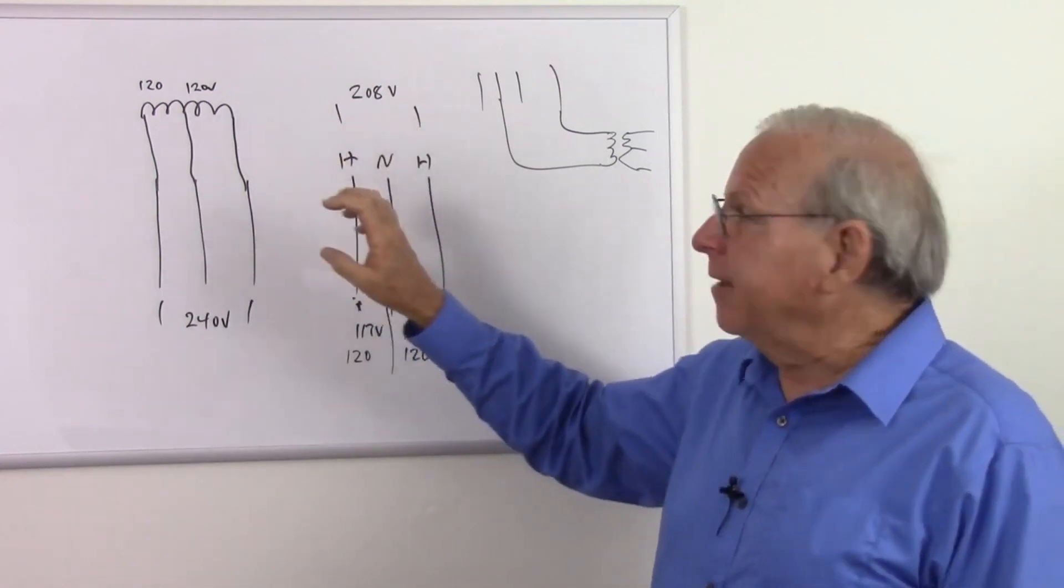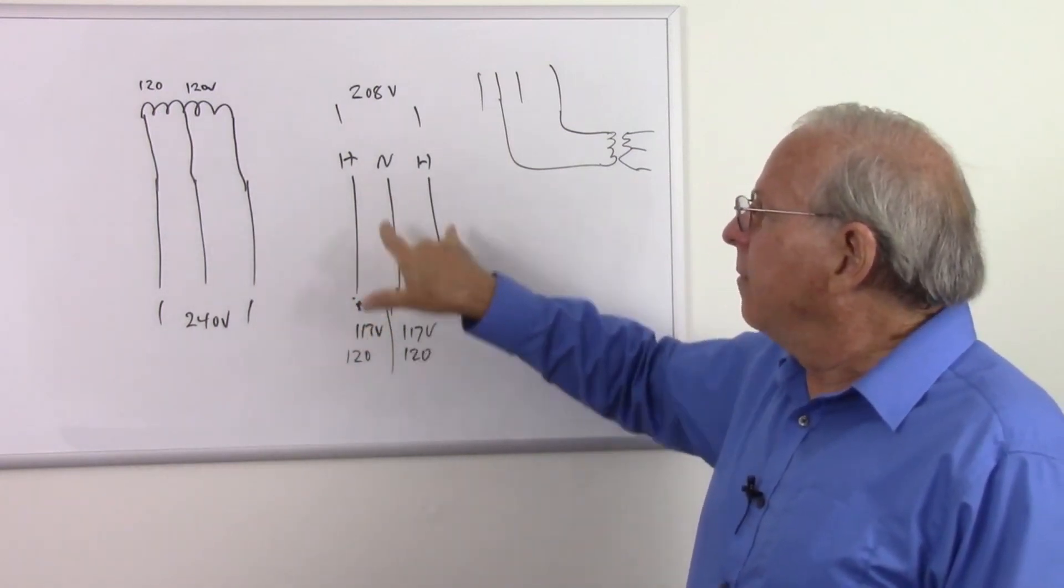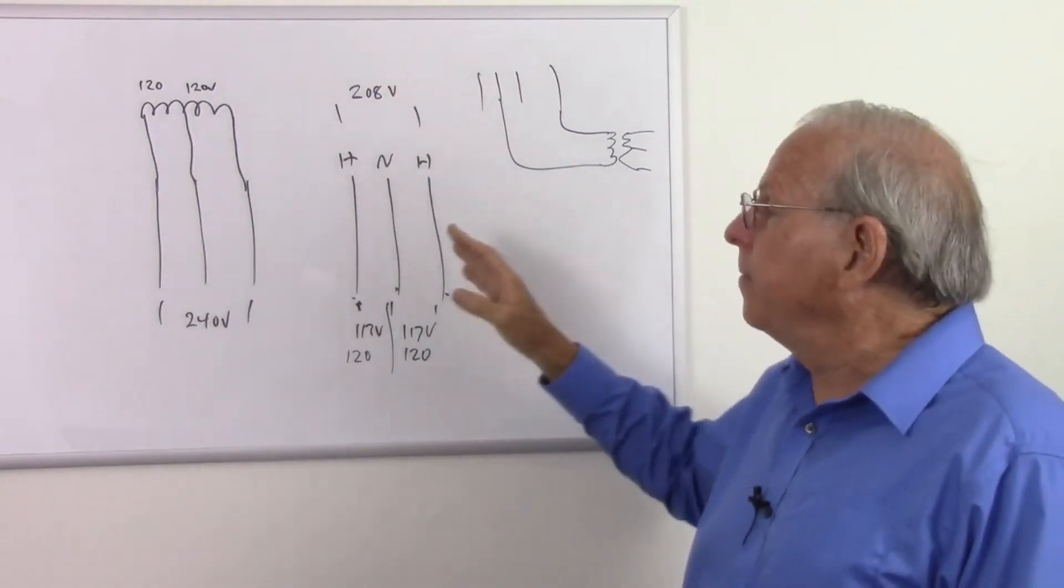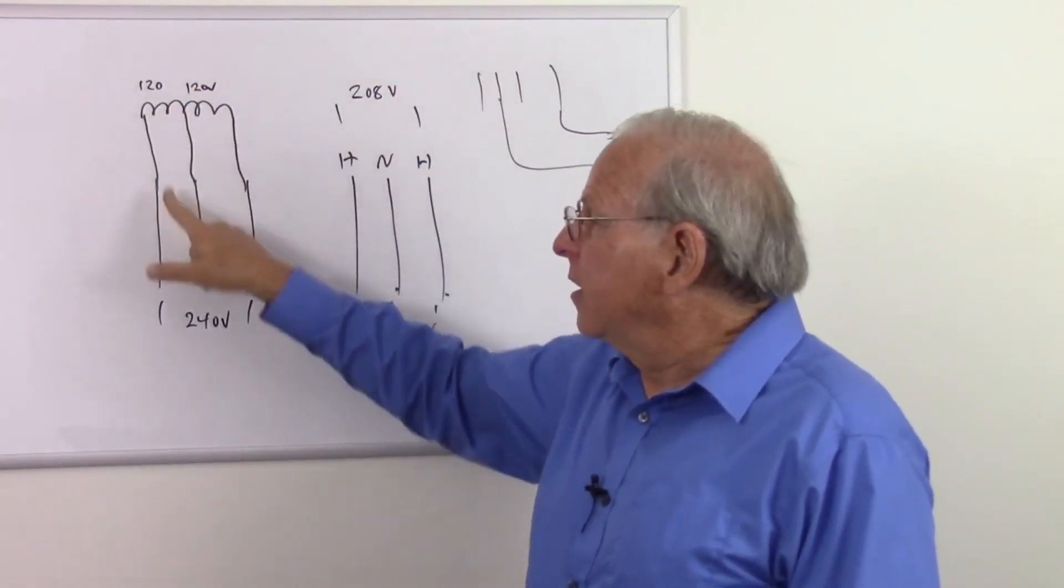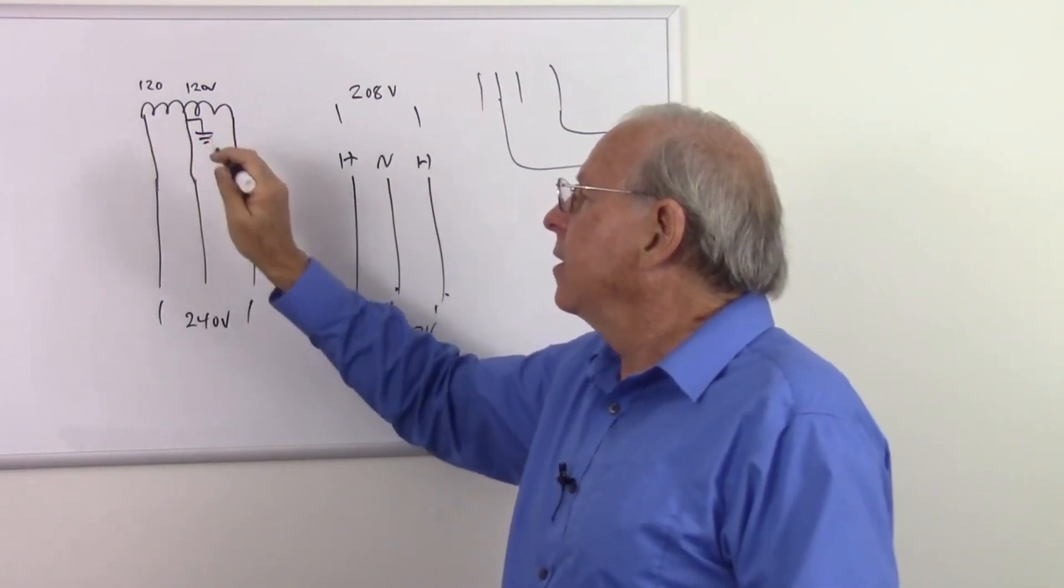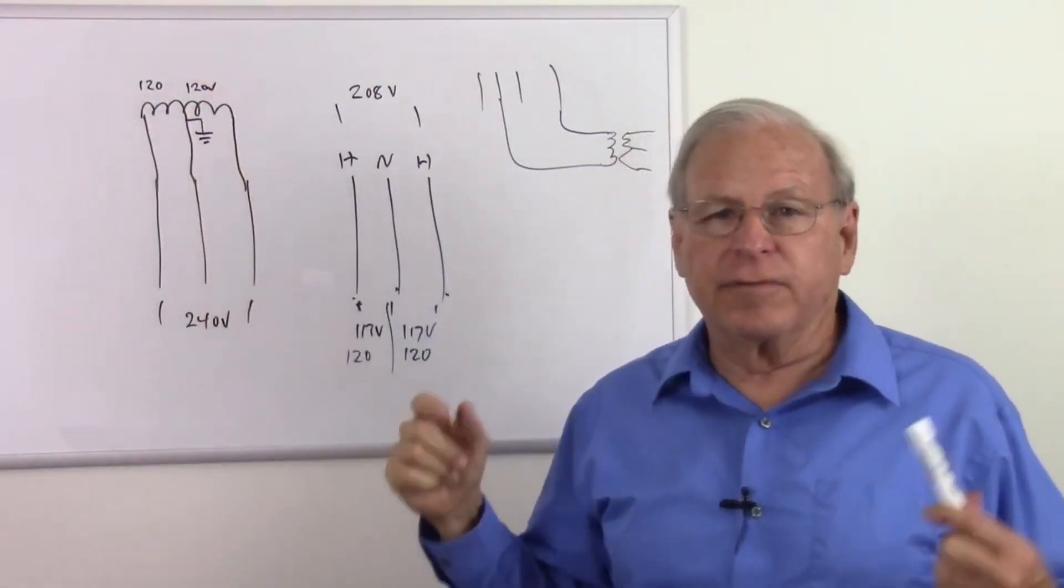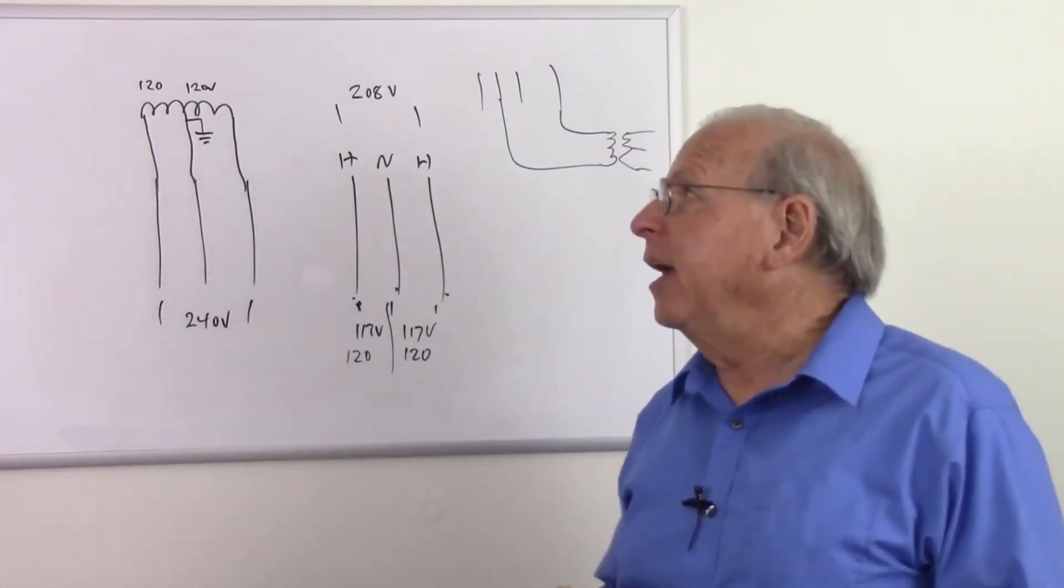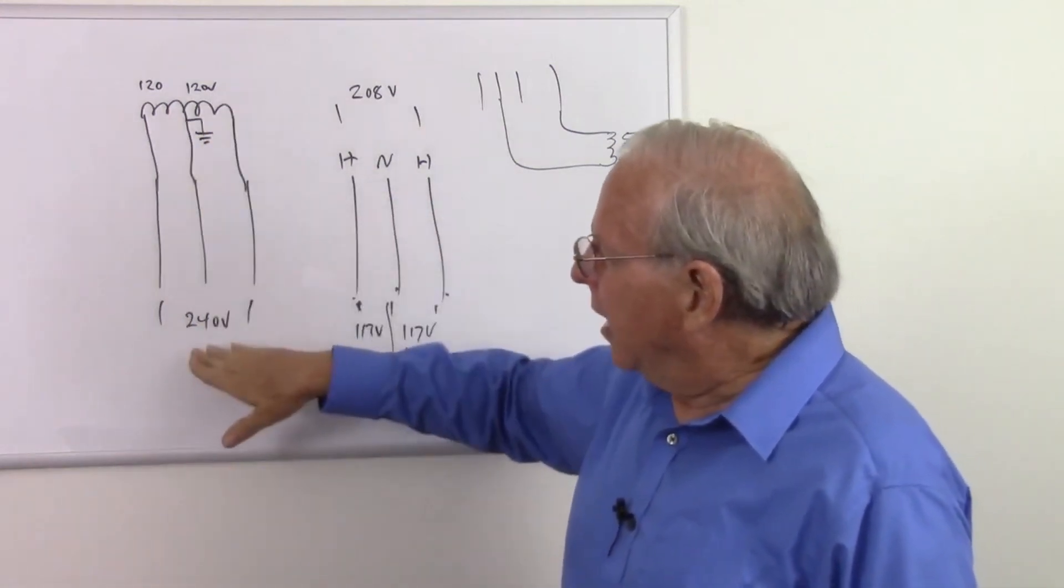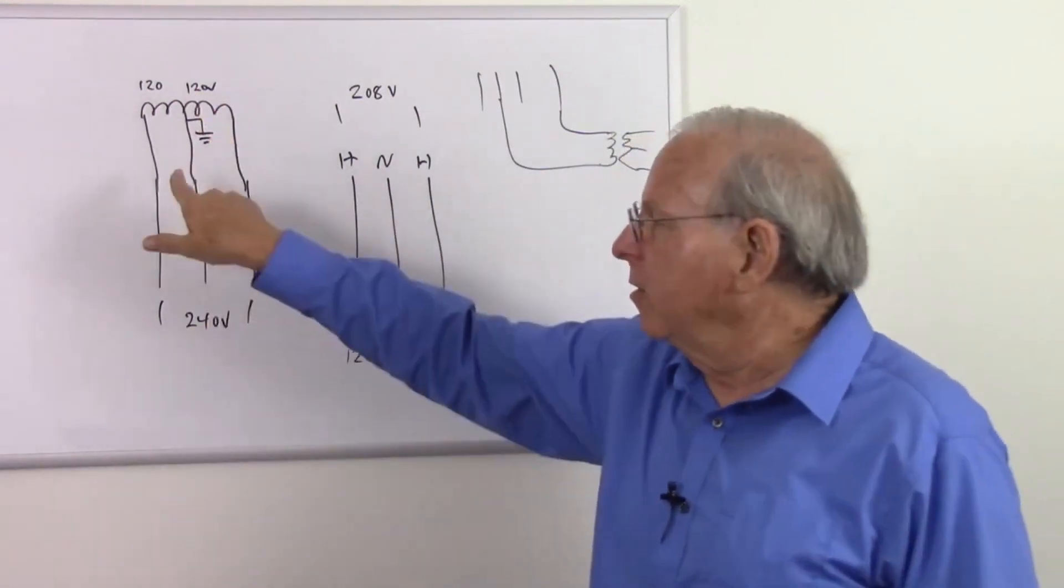So I just wanted to clarify that. So some places will get the two phase, in which case you would have 120 between the hot and the neutral, but only 208 between the other two because of the 120 degree phase difference that I explained in the other video. But when you get the split phase or the single phase, you're going to have just single phase power with a neutral coming down the middle. Of course, this is going to be grounded somewhere to make that work as it should. And so now we have 120, 120, or 240, or in the case of my area, that'd be 117, 117, and 236. Or did the math wrong. I can't do math in my head to save my life. But you would have twice the voltage across the two rails that you do from the hot to the neutral.